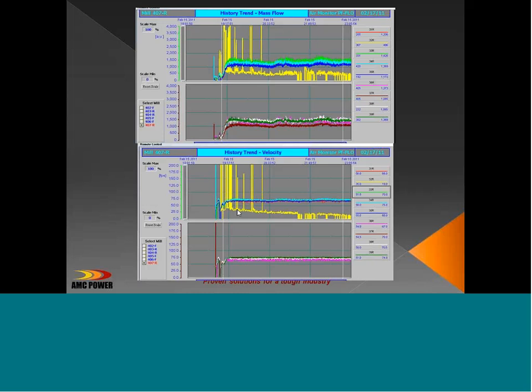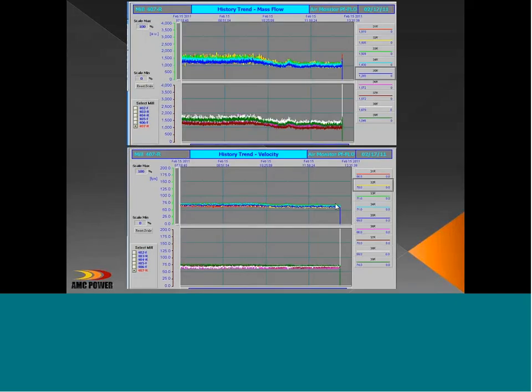By going backward in history, we could see before the mill came out, normally they purge the pipes. And as I showed before, very early in this presentation, what you should do when you shut a mill off is to leave the primary air running and sweep that mill and the pipes clean. And you can always tell that's done because if you look at the velocity, those velocities would increase before the mill ultimately came offline. The mass flows would be decreasing and the velocity would be increasing.